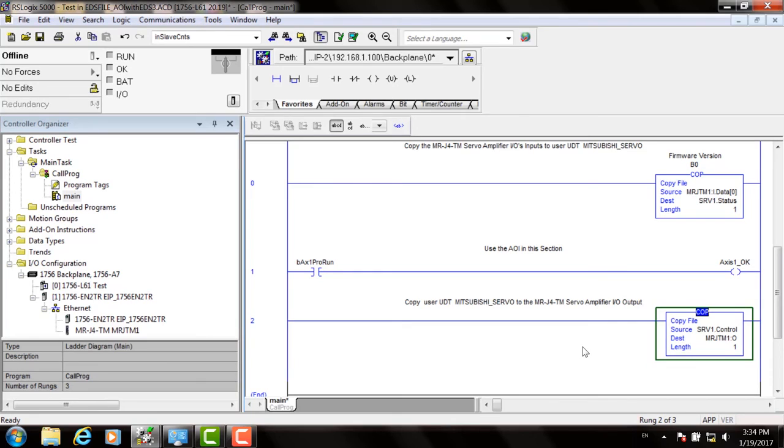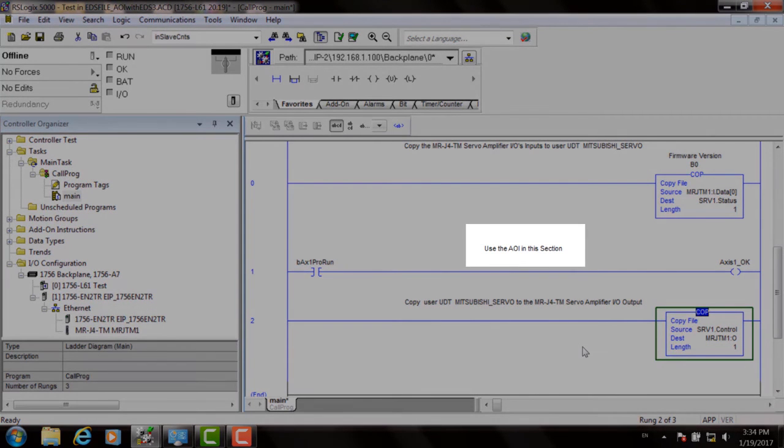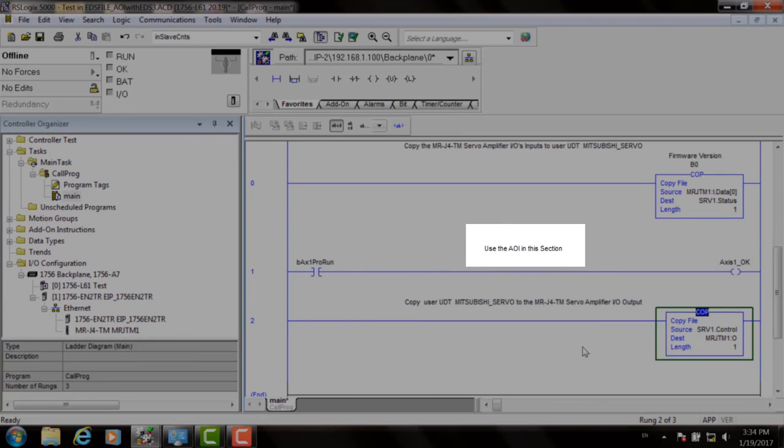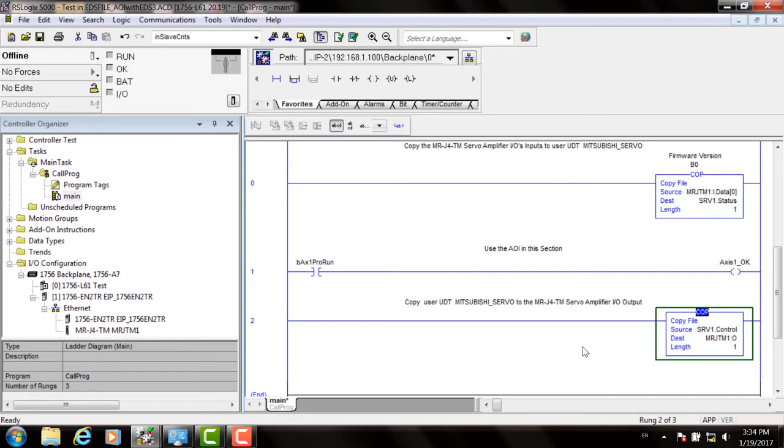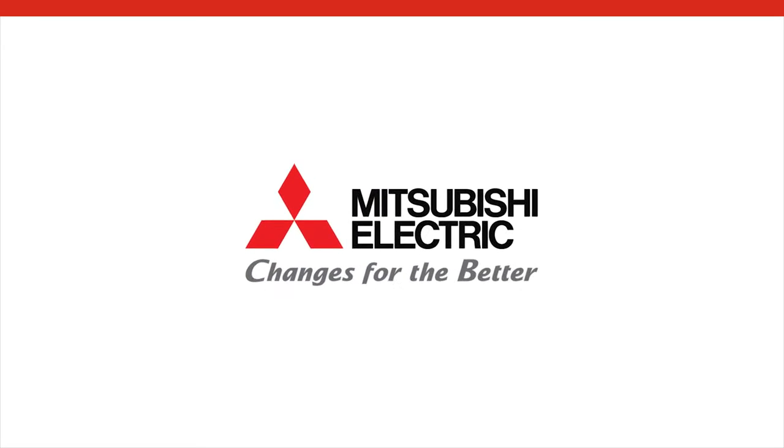Now that the AOIs are properly communicating with the servo drives, you can add additional AOIs to control the motion of the drives in the section highlighted here that says use the AOIs in this section. It's important to locate your additional AOIs between these two copy blocks to ensure proper data communications. Thank you for watching this Mitsubishi Electric Quick Tips video.